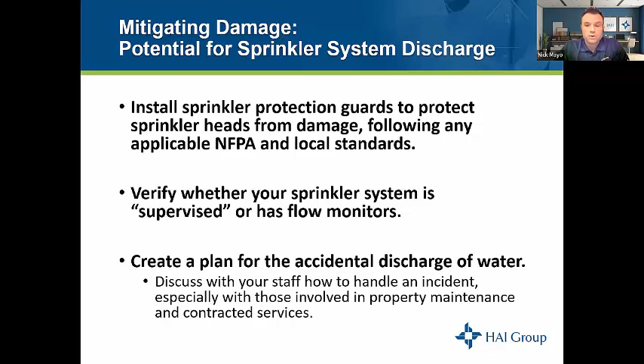So to start doing that, we need to determine if any on-site staff have experience or training to deal with a fire sprinkler discharge. Your authority having jurisdiction, you can consult with them in regards to our procedure for either closing water supply valves or chocking sprinkler heads before touching any part of the system. Always, please keep in mind, when in doubt, ask your fire department for recommendations on dealing with an activated sprinkler head. A fire department jurisdiction varies from state to state and county to county. So what works for one housing authority or one organization may not work for another, depending on the fire department and that authority having jurisdiction.